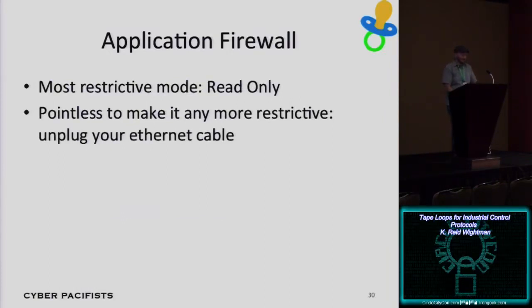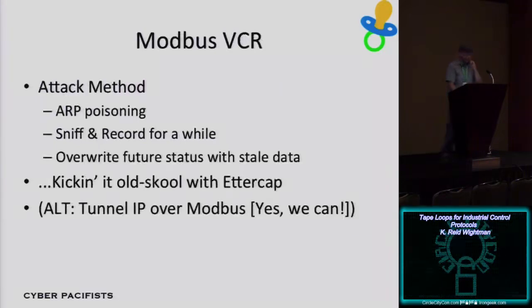The most restrictive mode is read-only, and it's pretty much pointless to make the firewall more restrictive than that, since if you can't even read information out of your PLC, why have it connected to a network at all? So the Modbus VCR is pretty simple.